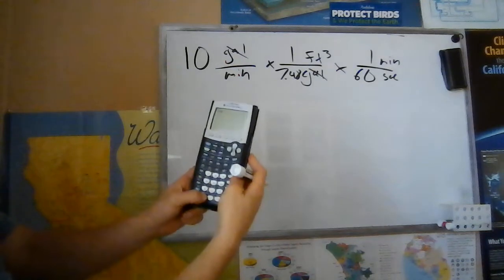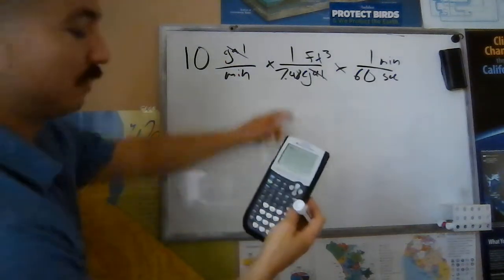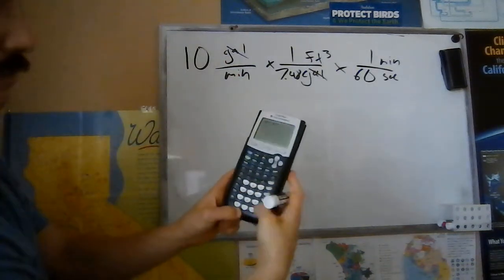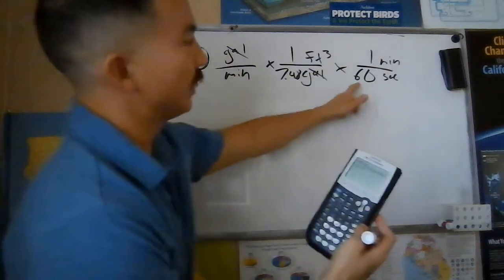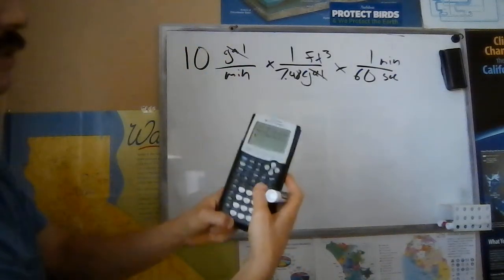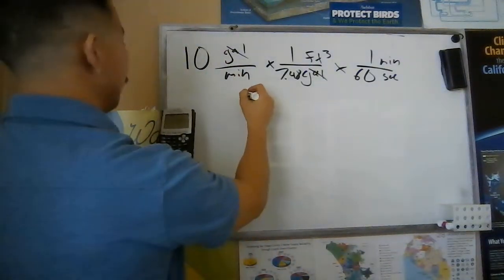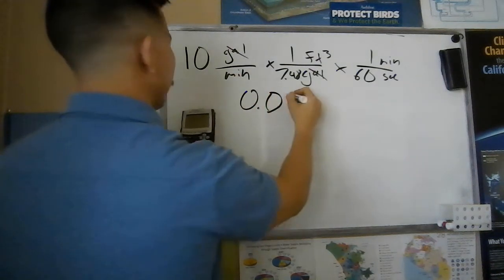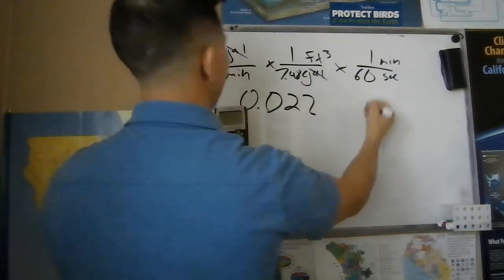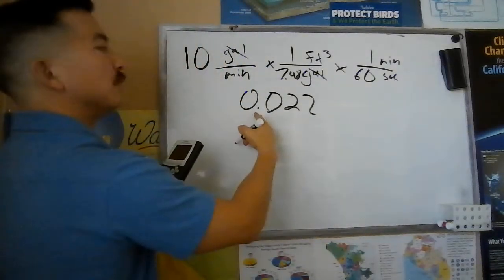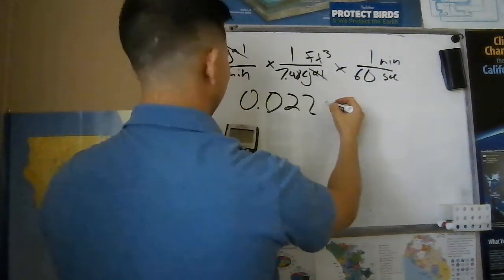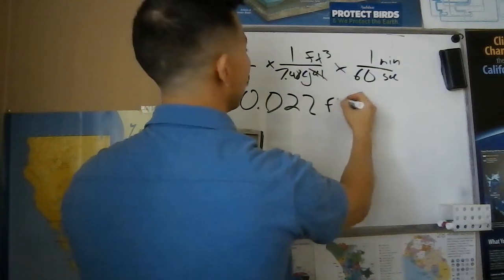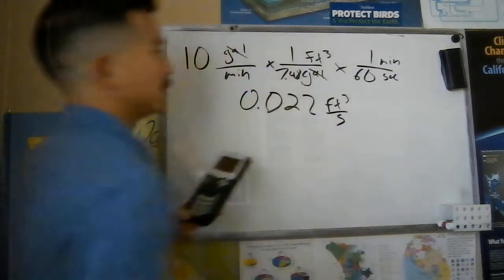So I'm going to take my calculator. I'm going to do 10 gallons per minute. I'm going to divide by 7.48 because it's on the bottom. I'm then going to divide by 60 seconds because it's on the bottom and I get 0.02228. We're going to put 0.022 and this is going to be our cubic feet per second.